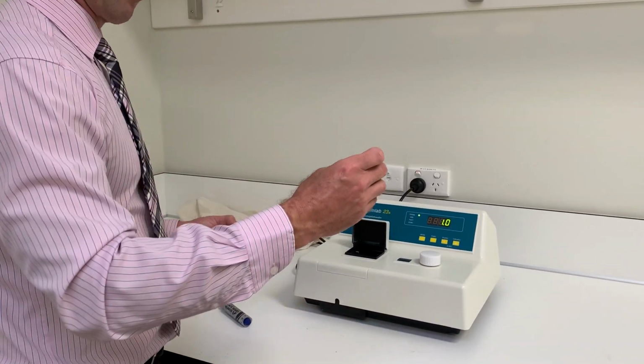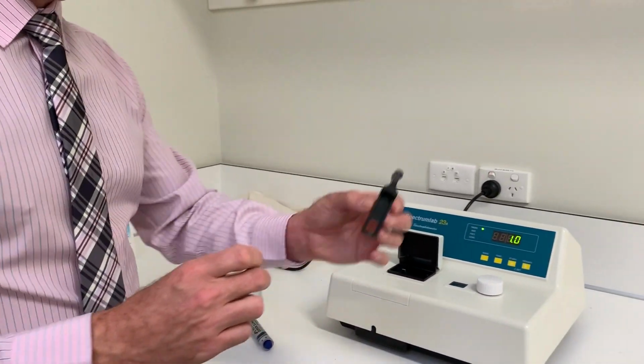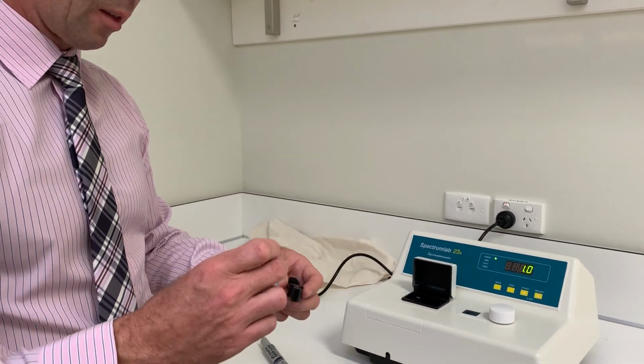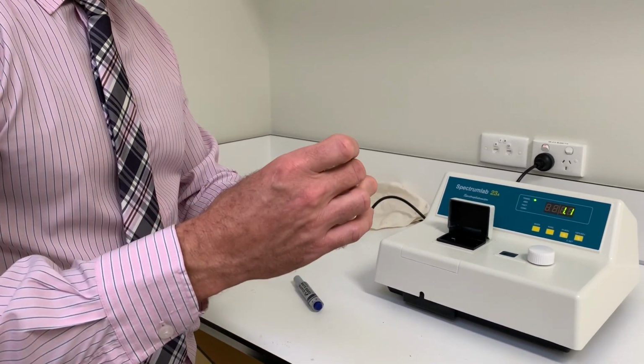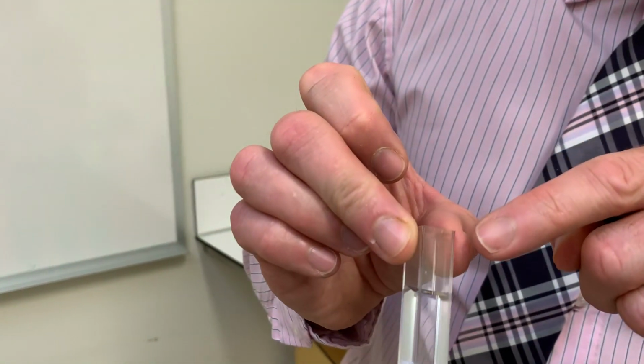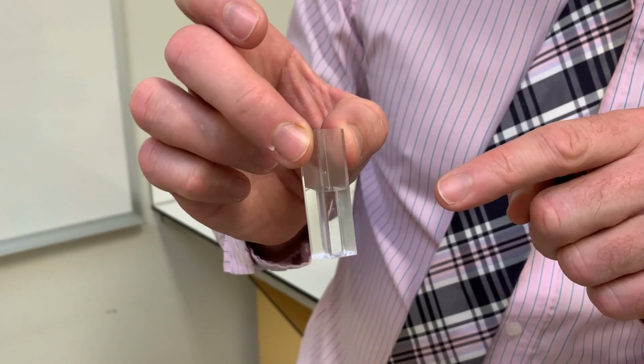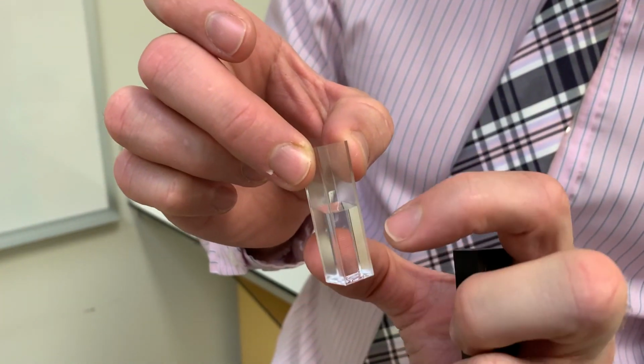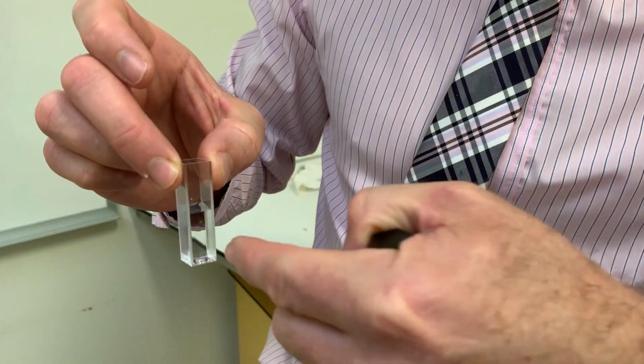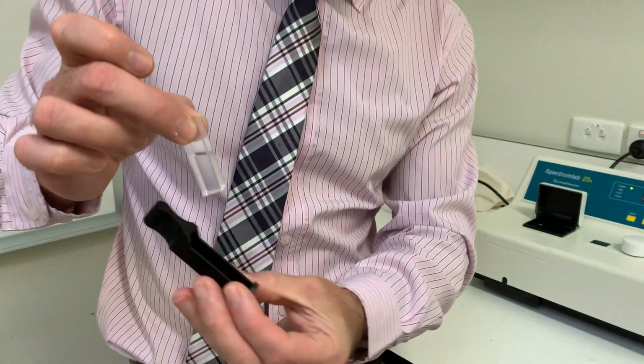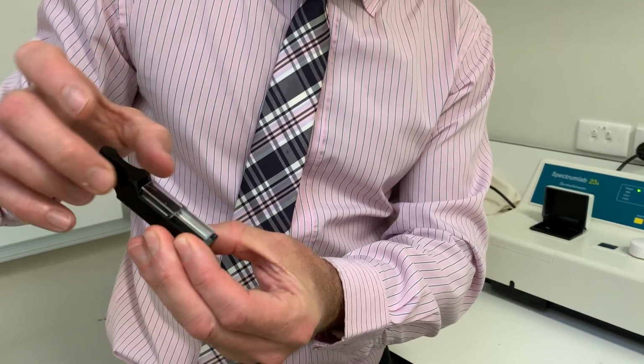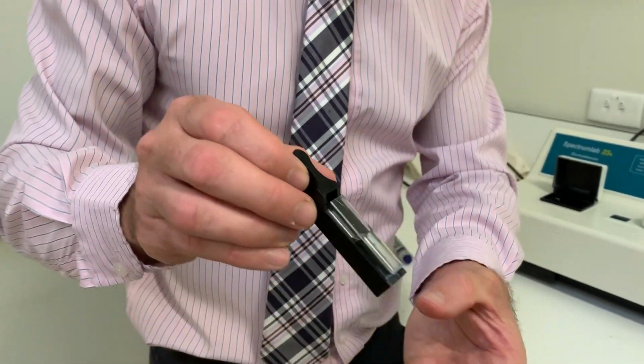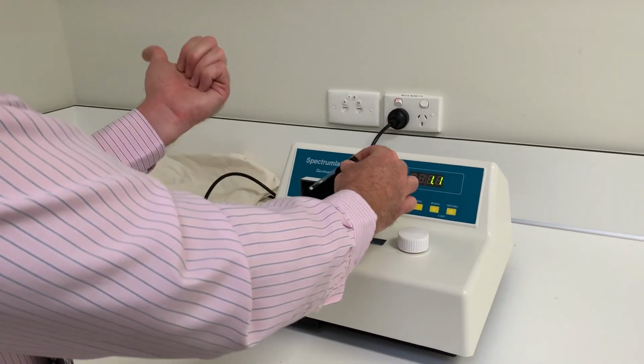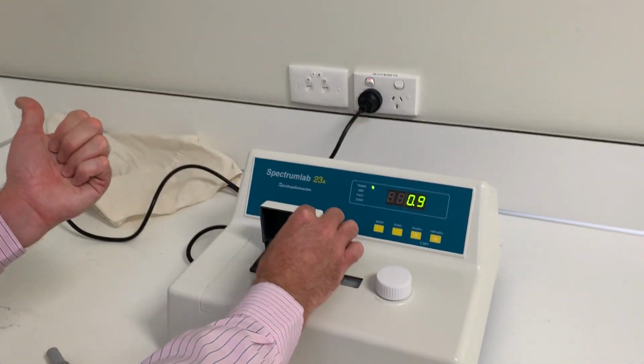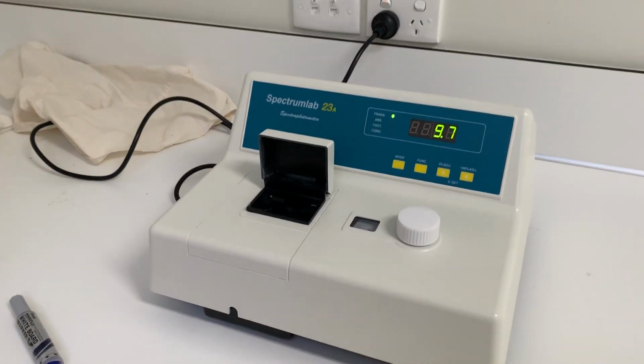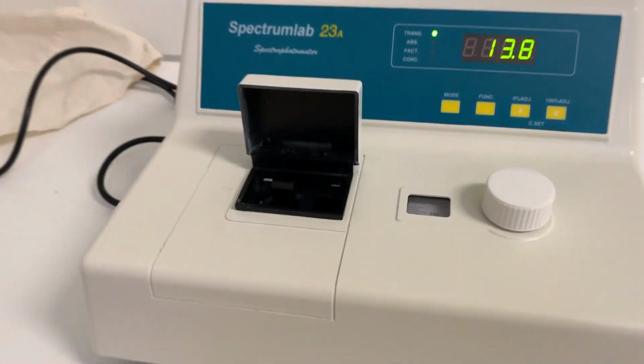So, first thing is, obviously the cuvette doesn't go in here just on its own. It's got to go in a cuvette cradle, in these ones here. When you're handling these things, you'll notice, I'll come up nice and close, there's a little arrow on the front. You can handle the cuvettes on the side, but this front face and the back face needs to be totally clean, because that's where the light is going to go through. So you put it in the cradle so that the arrow is sitting at the front there. And then the arrow will be facing the left-hand side, and you just slide it down into that cuvette holder. Cool.